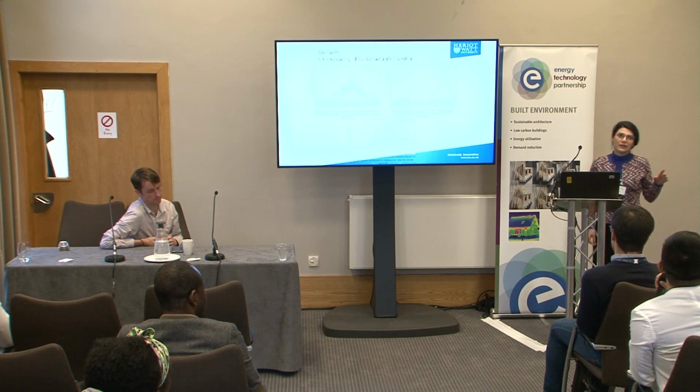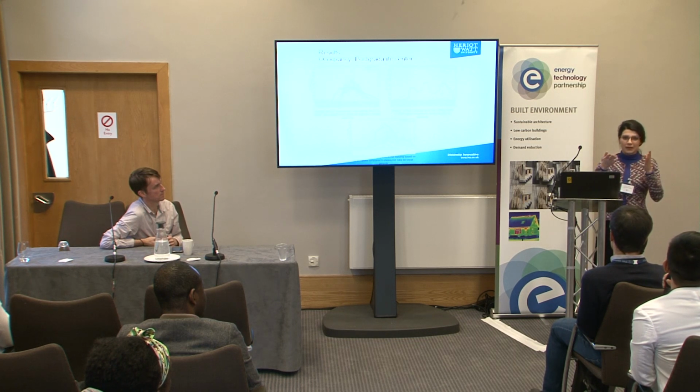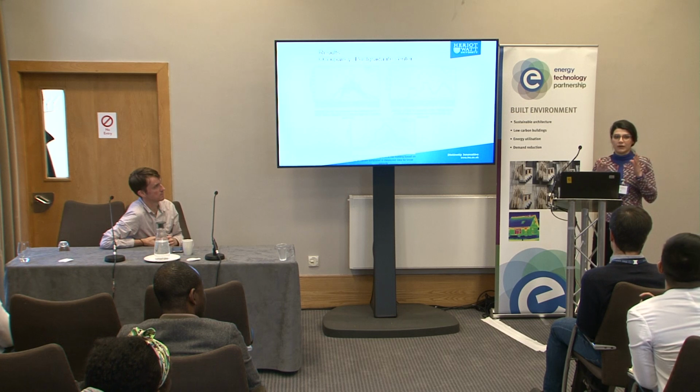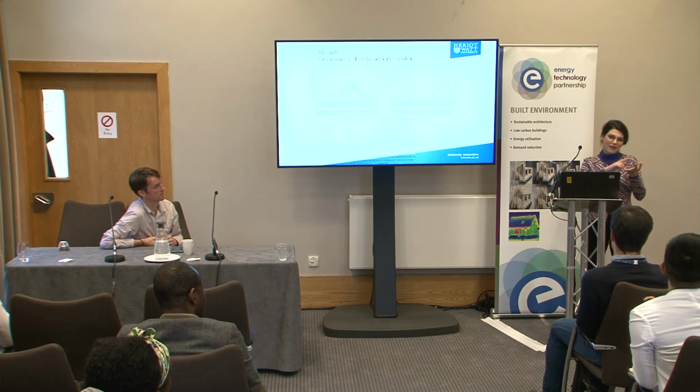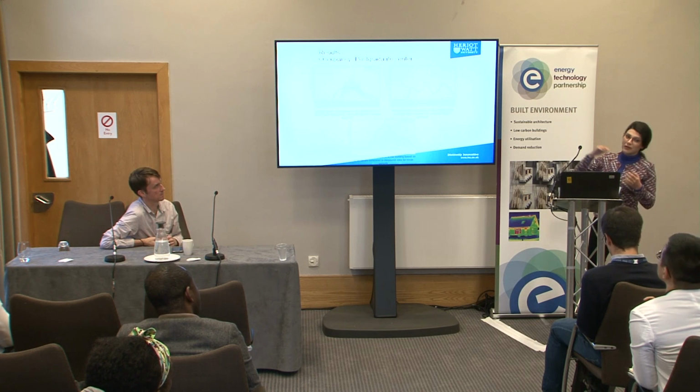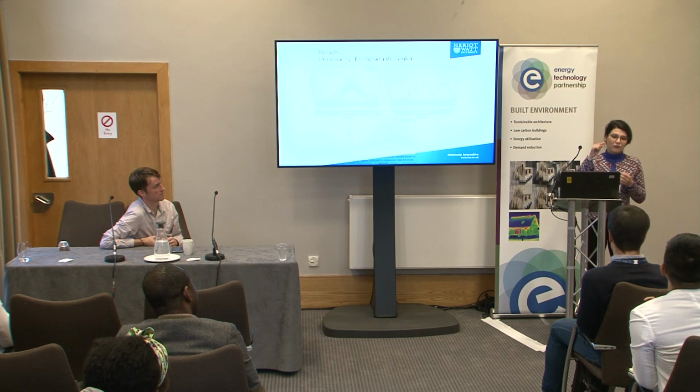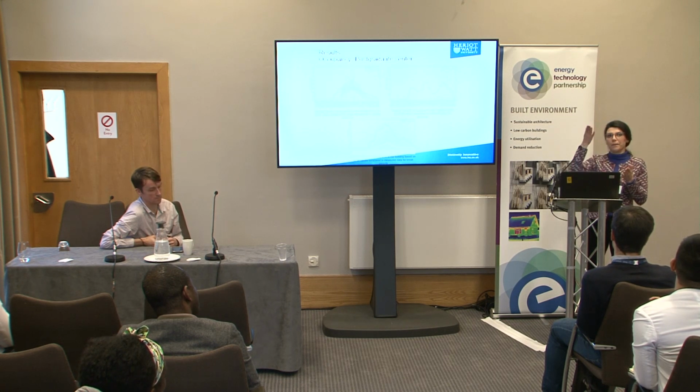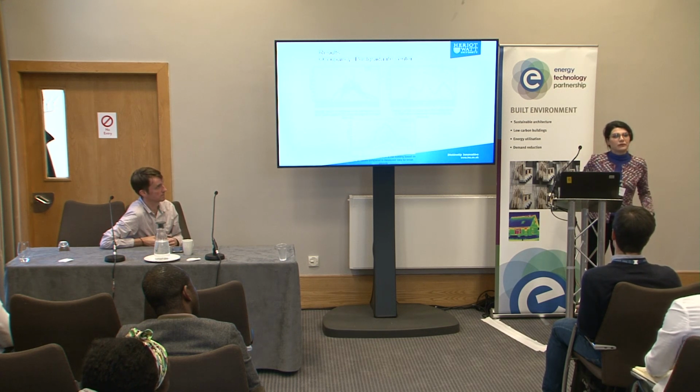Well, you know, NCM profiles and density values are provided in the guidelines. You have different space types and the square meter of each space type. You have the occupancy density, and you have the diversity factor for each time step. So you can easily calculate the numbers in each space, and then add up for the building level occupancy.